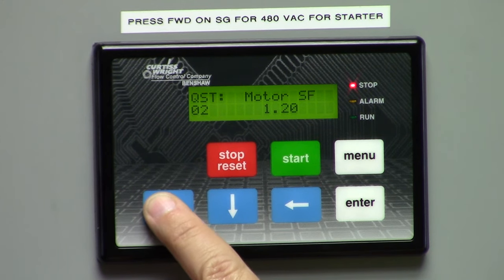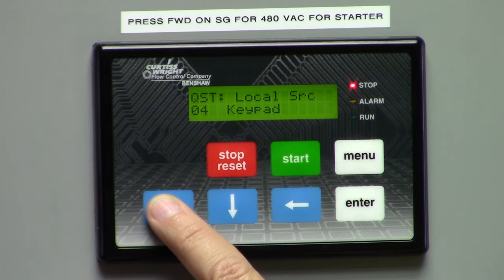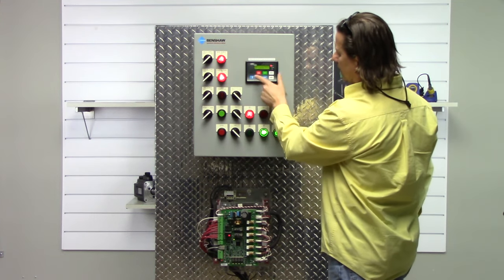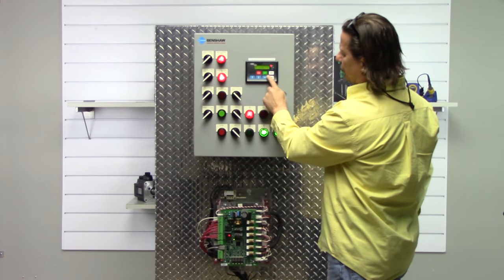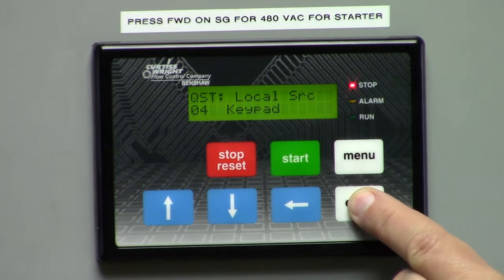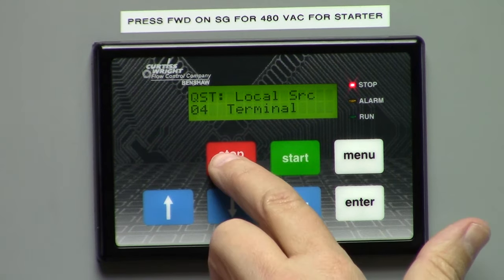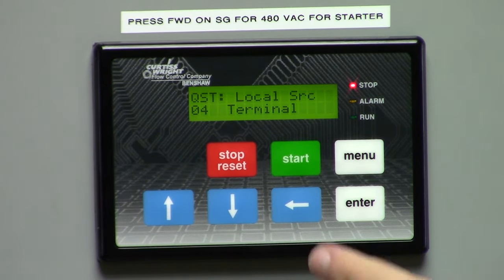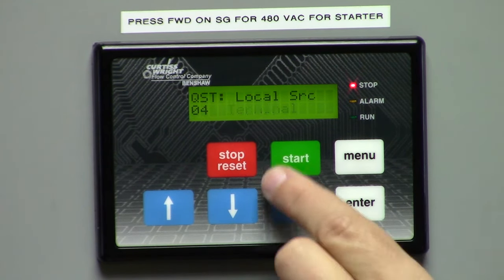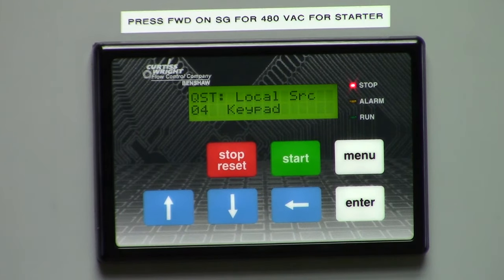The next one up is service factor. Again, you enter everything in here that matches your nameplate. Here is running overload — you can program that to whatever class overload you want. The local source tells you where you're going to start and stop this product. Right now we have it set for keypad because I want to use the start and stop buttons here on the keypad. However, if I wanted an external input to start it, I would simply change this to terminal, then enter. Now it won't start or stop with the keypad buttons because it's looking for the start signal somewhere else. So I'm going to put it back to keypad, enter, and now it will start and stop from here.